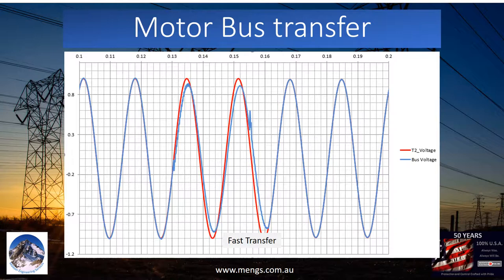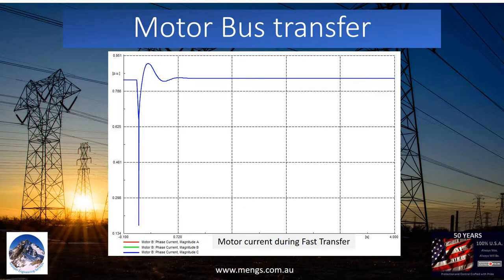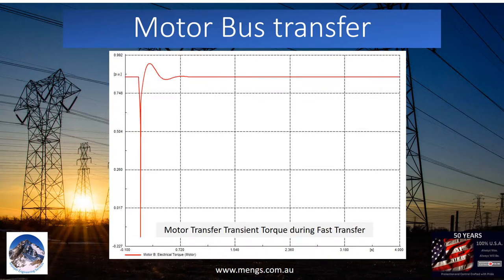In the first few cycles after disconnection of the motor bus from the main source, the motor bus frequency is stable and close to network frequency. If the new source is in sync with the motor bus, the transfer can happen immediately. Having a fast sync check is essential to perform fast transfer; the sync check time should not be more than 10 to 15 milliseconds. In the case of fast transfer, the motor current won't change much — the re-acceleration current is approximately nominal current. The transfer transient torque is low, as the new source connects with very marginal phase angle difference.